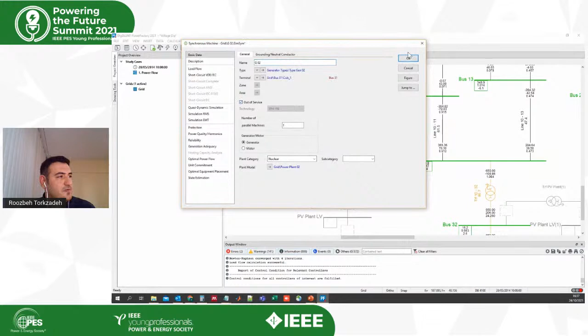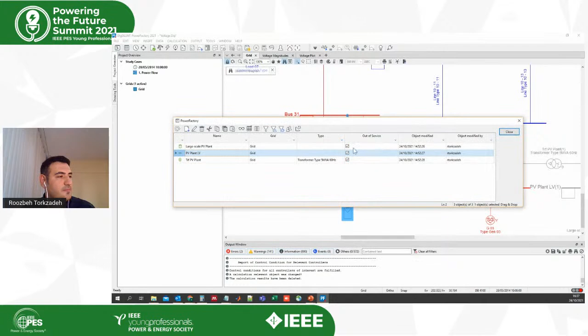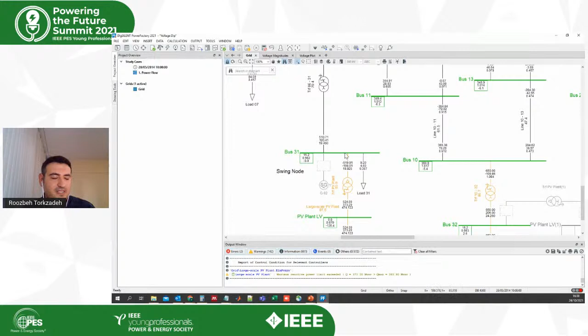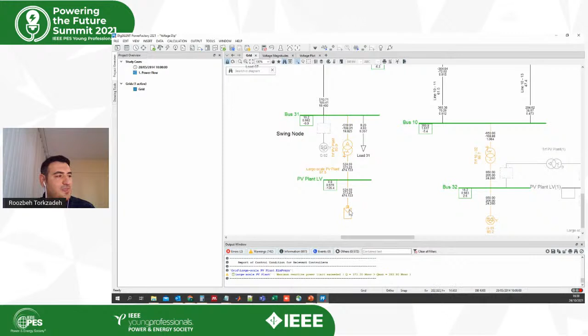Let me run a load flow here. You can see that the active power from this unit, the transit power through this transformer, is about 500 megawatts, and the voltage at this node is 0.98. When I put this one out of service and switch the renewable plant into service, you can see the same amount of power flowing through this transformer and the same voltage value. So practically, from the load flow perspective, these two generations are equal.